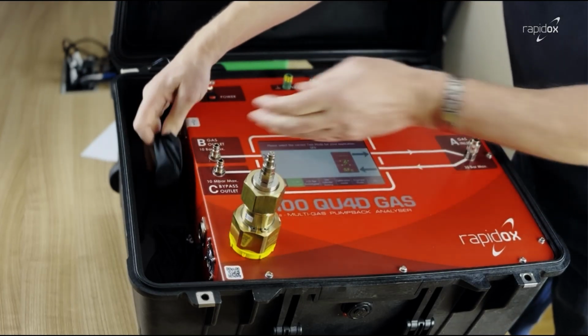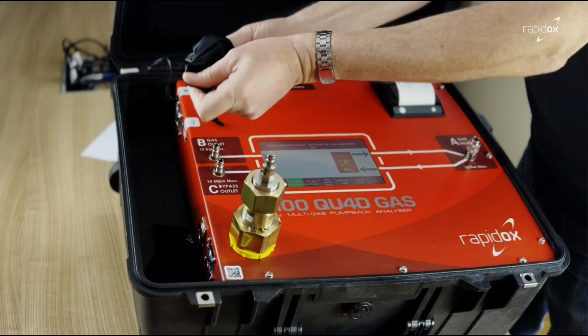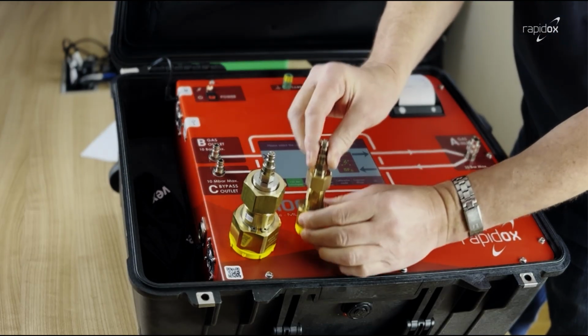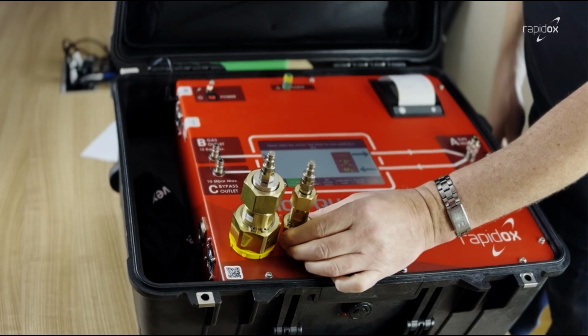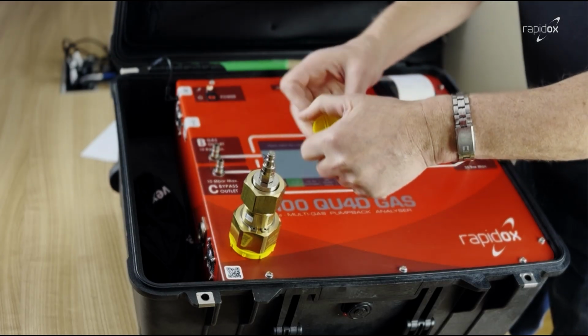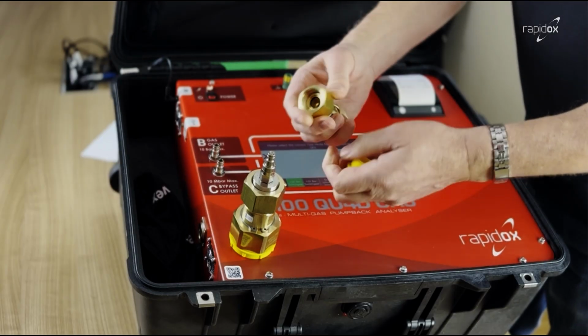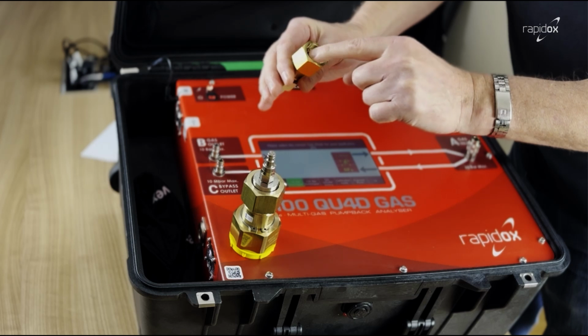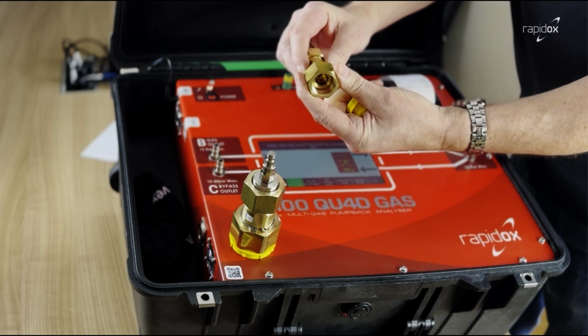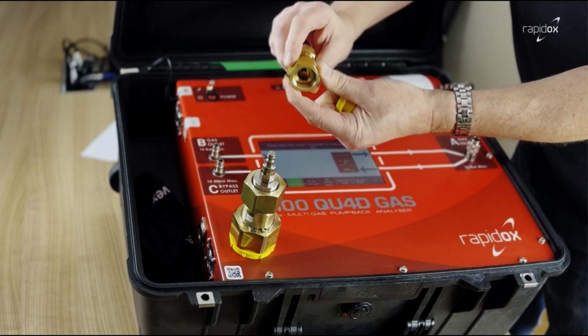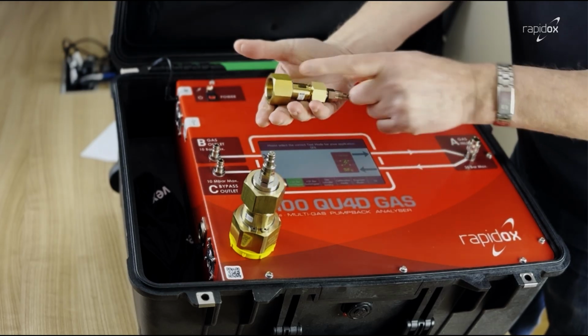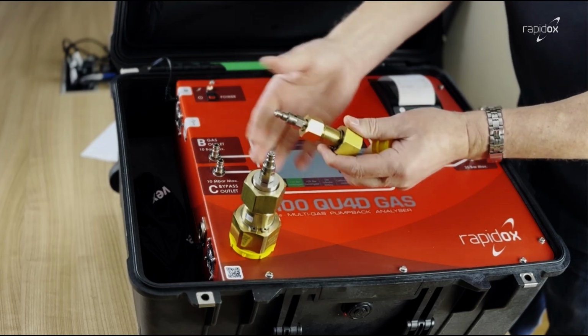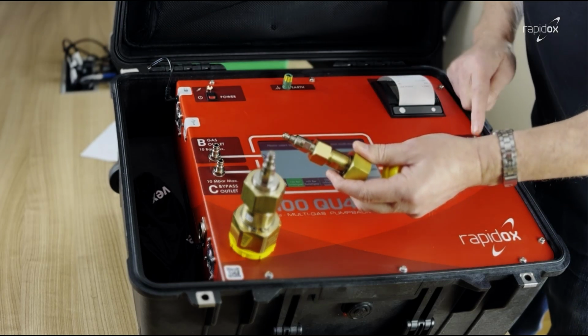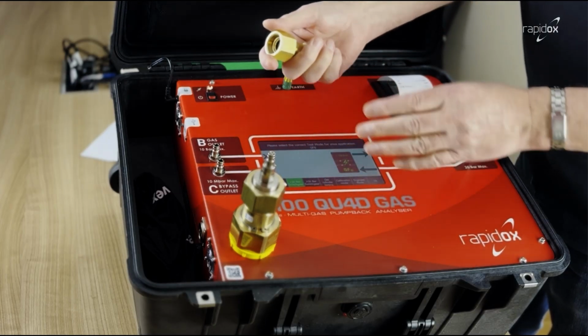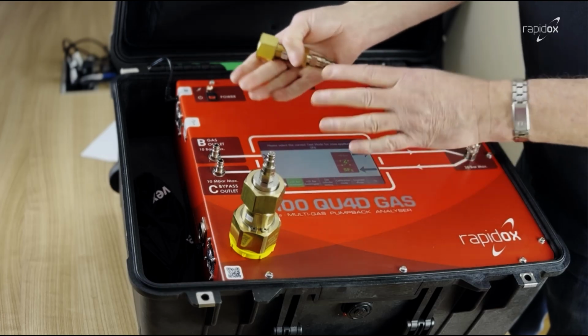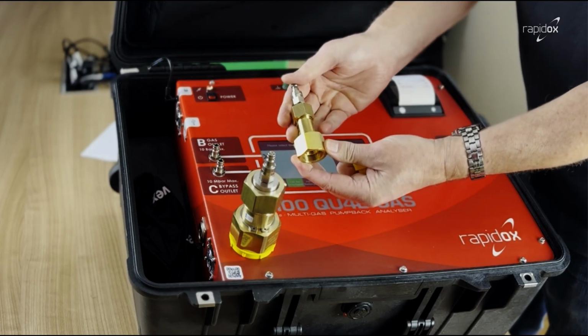The DN8 is probably the most common one that we use, and this is a lot smaller than the DN20, as you can see, but they actually have the same connector on the top. This is the part that you connect to your test point, which is the famous Dilo tongue and groove coupling fitting, which minimises or eliminates any gas escaping when you attach it. So this needs to be attached onto the test point, tightened with a spanner, and then you can take the hose and attach the female onto here and the male onto here, and then you are ready to begin the test, as the pressurized gas will now enter the analyzer and we can start doing the testing, which is shown in a different video.